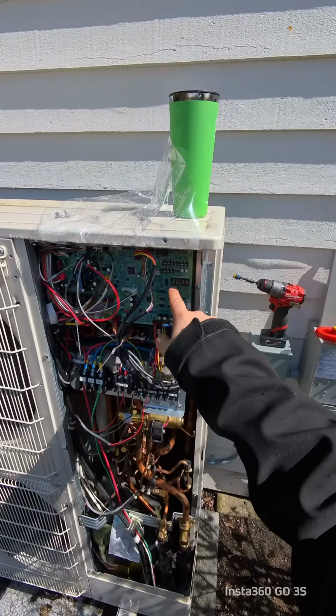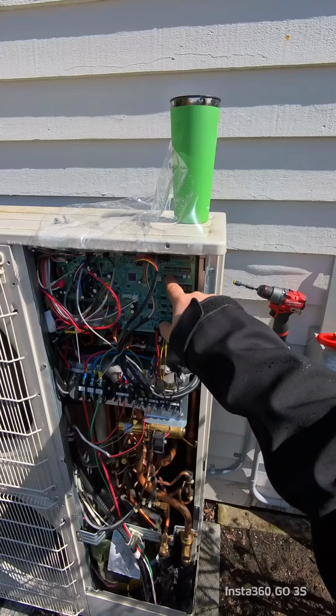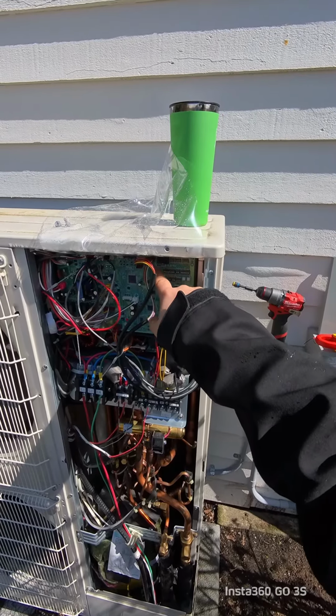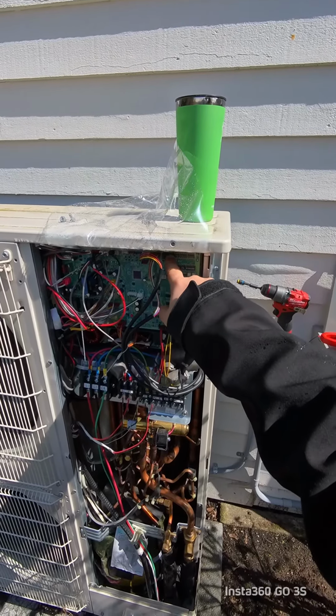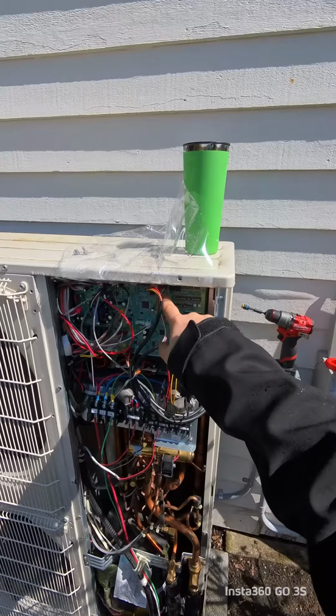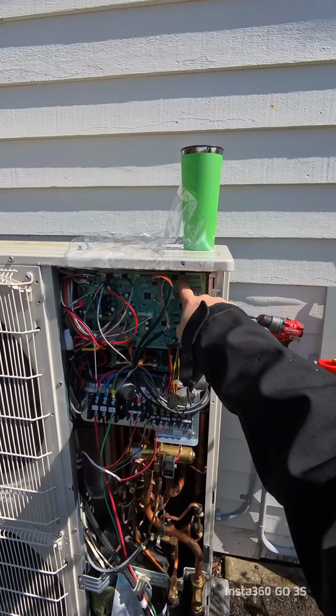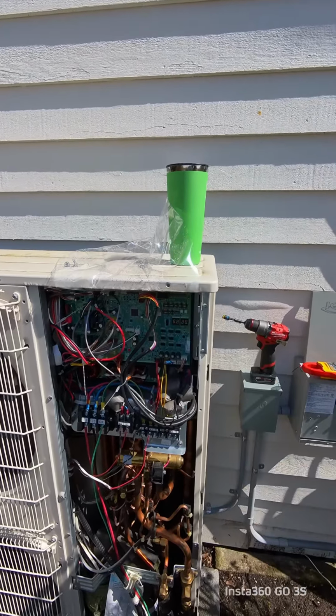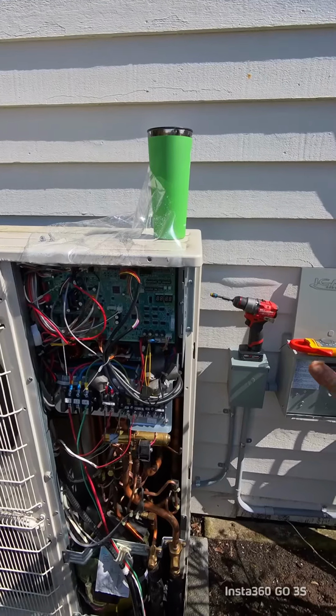Make sure your dip switches are correct. So if you have a branch box, you'll need to flip this. Make sure your rotary dials are set correctly. So we're at 51 out here, and you're going to be 01 inside when we have one branch box.